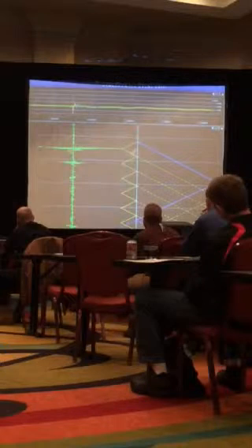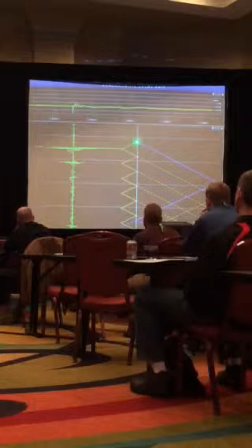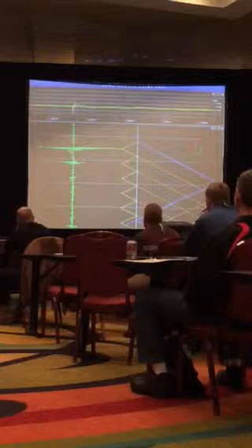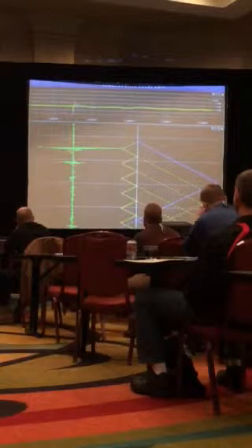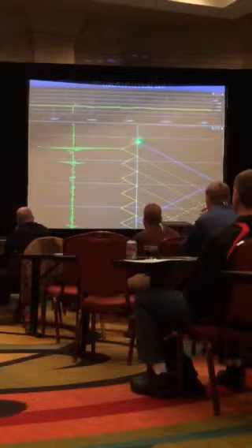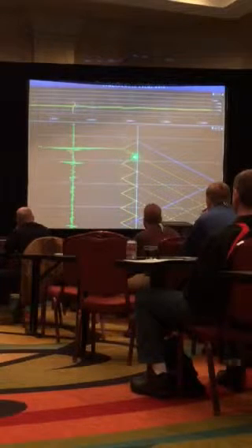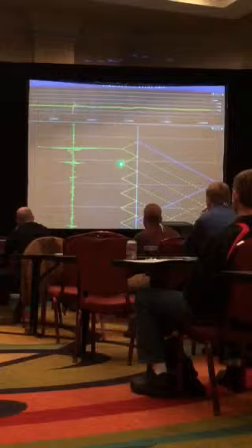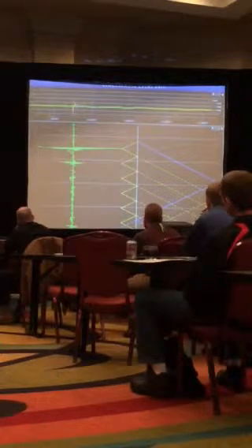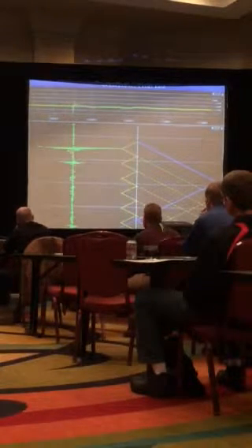So what we have here is time running down the page. Here's a point somewhere between me and you. It's pretty close to me, pretty far from you on this line. We might assume it to be 100 miles for fun. So a fault occurs right here, and the traveling wave comes and bounces off my bus, goes out, bounces off the fault, bounces back, so I start to see these blips. They don't look anything like 60 hertz, do they? Because they're not. They don't really care what's going on with respect to the 60 hertz.